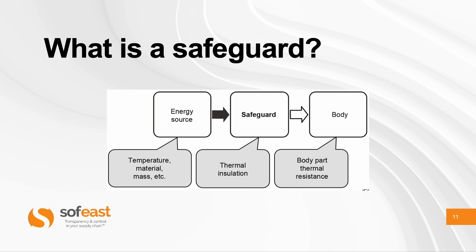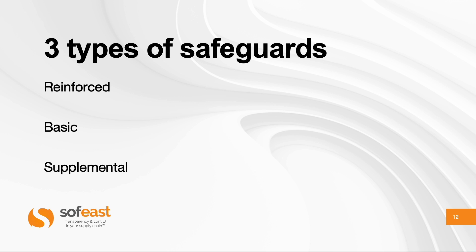Another very important concept is the safeguard. You have an energy source that transfers to the body — that's a hazard. You put a safeguard in place: for example, if the product is very hot, you insulate it to protect the body. A safeguard avoids, mitigates, or makes it less likely that the hazard and its effects — injury, fire, etc. — occur. There are three types of safeguards: reinforced, basic, and supplemental.